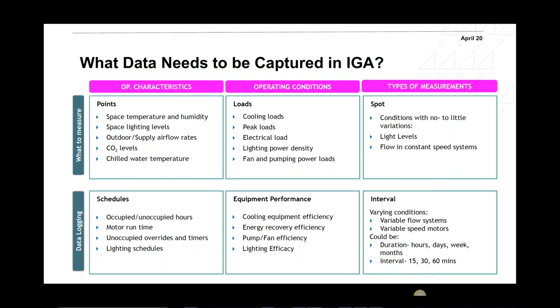I can put a BTU meter on the chiller to check what the cooling load is. I would probably put it there for a month if I can. What are the peak loads? Electrical load: I can put power analyzers on the MDBs or the MCCs, or any kind of equipment I need to take measurements of. Lighting power density: taking the watts per square meter in a specific room, I can compare it to ASHRAE 90.1 to see if I am above or below the standard requirements. Fan and pumping power loads.